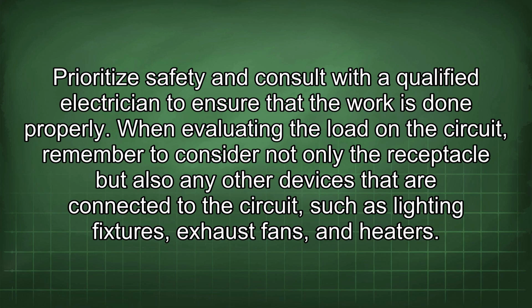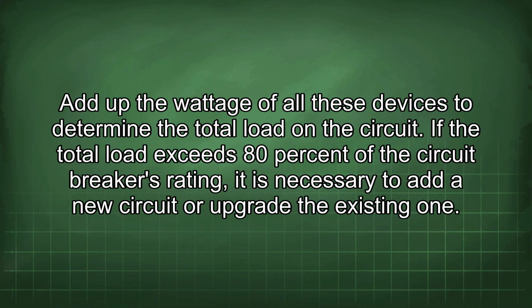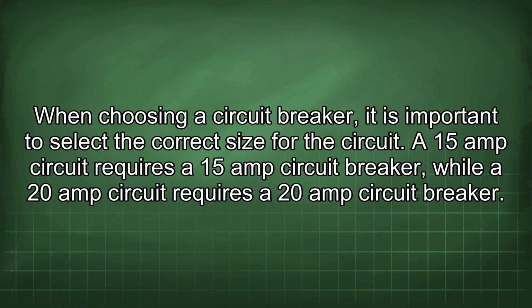When evaluating the load on the circuit, remember to consider not only the receptacle but also any other devices that are connected to the circuit, such as lighting fixtures, exhaust fans, and heaters. Add up the wattage of all these devices to determine the total load on the circuit. If the total load exceeds 80% of the circuit breaker's rating, it is necessary to add a new circuit or upgrade the existing one.